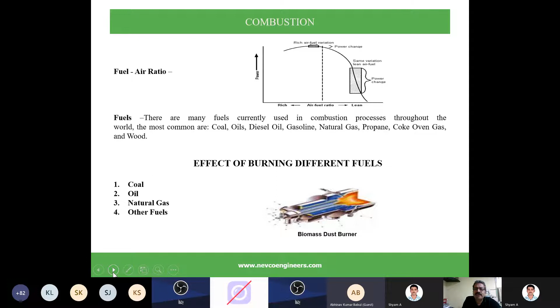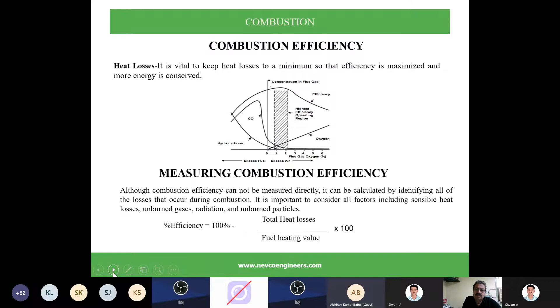It depends on the fuel. The effect of burning the fuel is the heat losses. How to calculate combustion efficiency? Combustion efficiency cannot be measured directly; it can be calculated by identifying the losses that occur during combustion. It is important to consider all factors, including sensible heat losses, unburned gases, radiation losses, and unburned particles. So efficiency equals 100 minus total heat loss divided by the fuel heating value, the calorific value of the fuel, multiplied by 100. Now, typical combustion process efficiencies.